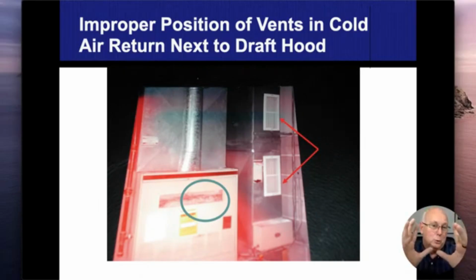What's a common solution if you make the ductwork too small and you're restricting the airflow coming back to the rooms? And when I mean ductwork, I'm talking about the return ductwork, all right? Then that blower fan depressurizes that ductwork and causes it to collapse. And usually the fan builds up speed slowly, so the sucking in part is not as noticeable. But then when the fan turns off, you hear that big whoomp, and that's all the ductwork coming back in.